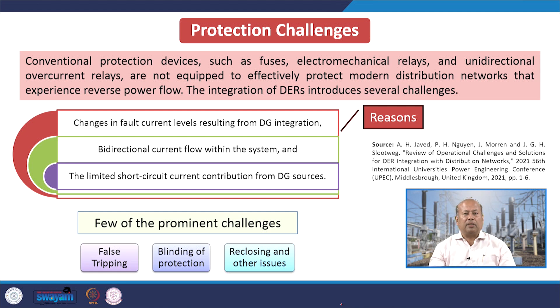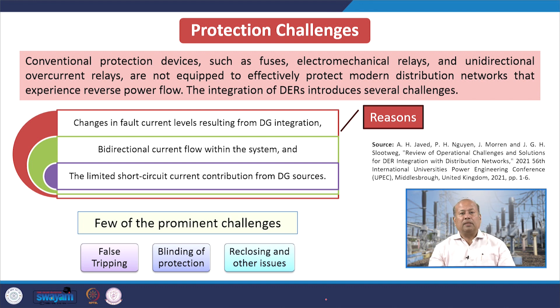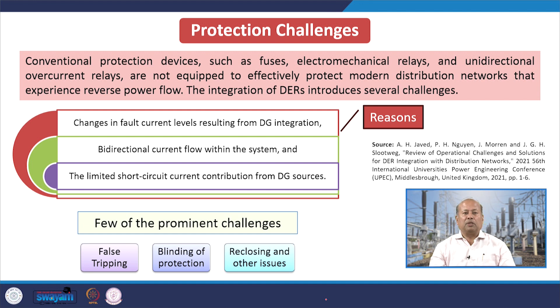Regarding protection challenges: conventional protection devices such as fuses, electromechanical relays and unidirectional over-current relays are not equipped to effectively protect modern distribution networks that experience reverse power flow. The integration of DER introduces changes in current levels resulting from DG integration, bi-directional current flow within the system, and limited short circuit current contribution from DG resources. Common prominent challenges due to renewable integration include false tripping, blinding of protection mechanism, and reclosing issues.